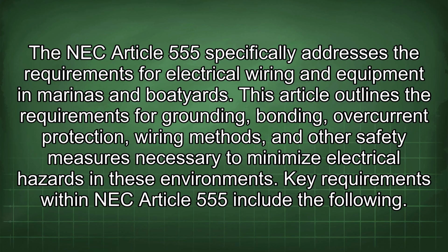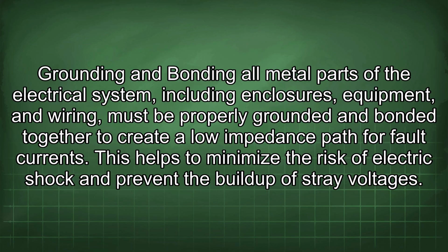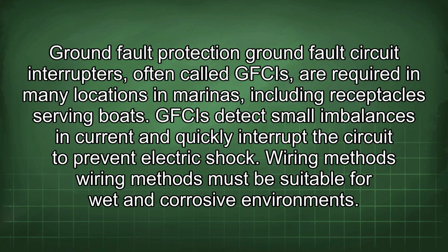Key requirements within NEC Article 555 include the following: Grounding and bonding. All metal parts of the electrical system, including enclosures, equipment, and wiring, must be properly grounded and bonded together to create a low impedance path for fault currents. This helps to minimize the risk of electric shock and prevent the buildup of stray voltages. Ground fault protection. Ground fault circuit interrupters, often called GFCIs, are required in many locations in marinas, including receptacles serving boats. GFCIs detect small imbalances in current and quickly interrupt the circuit to prevent electric shock.